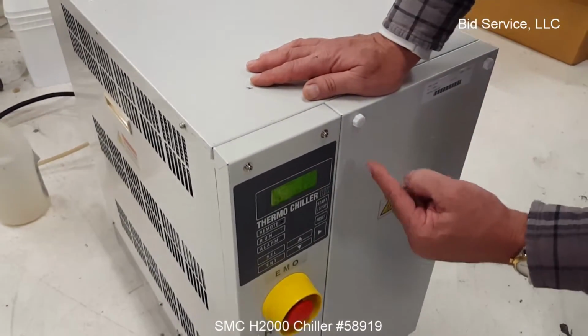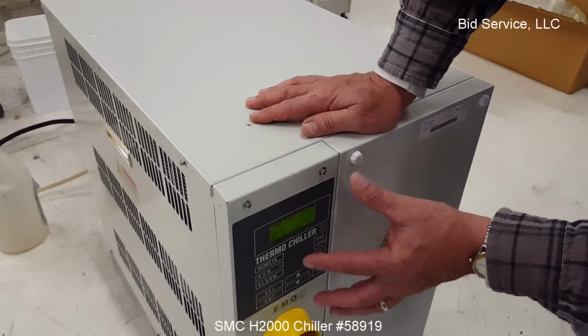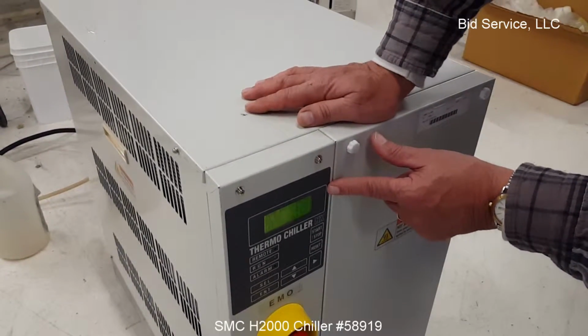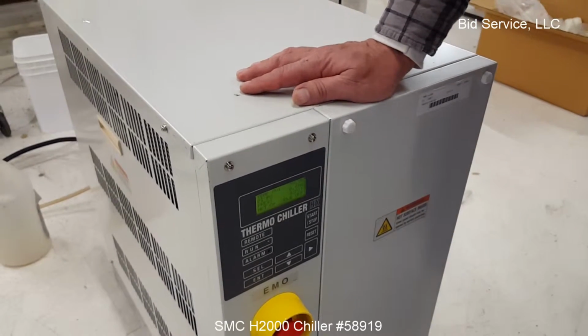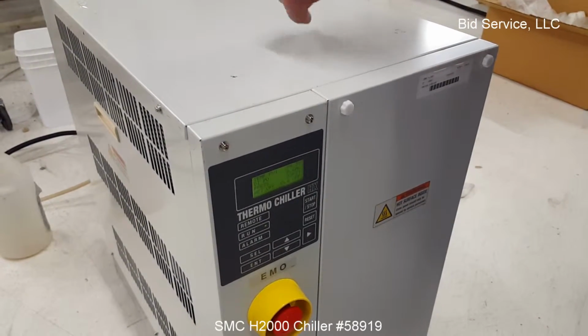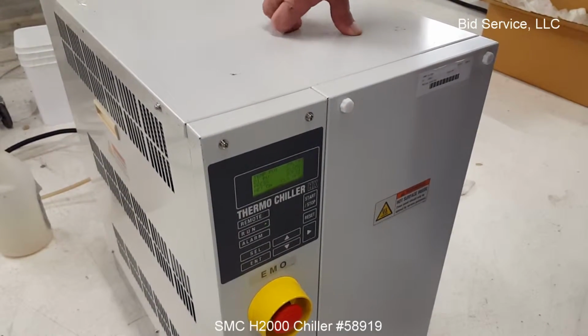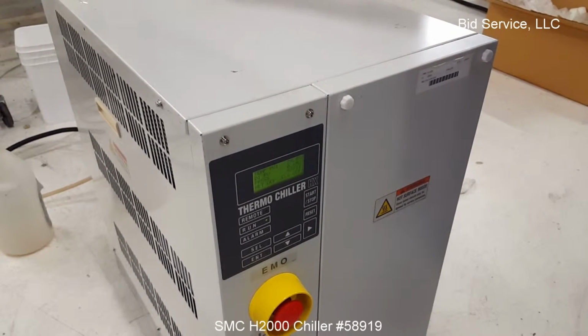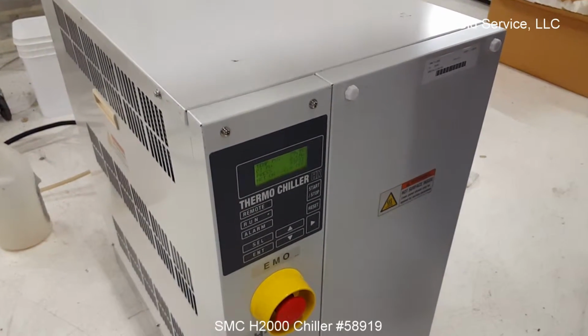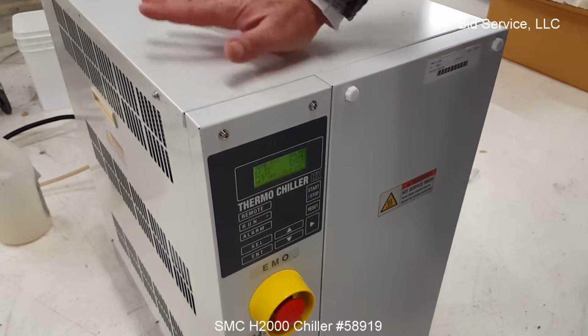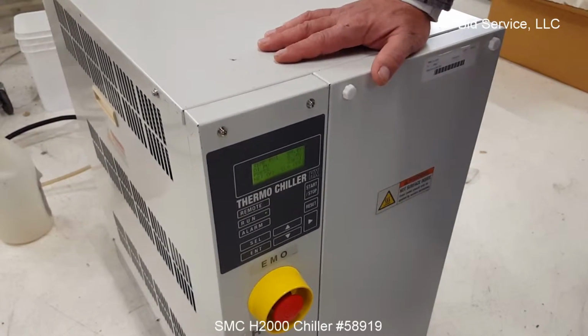And I have it up at the high end so you can see that it can go up there and control, which it is, which means that you have the reprocessed fluid recirculating through the heat exchanger, and you have the chiller from an external chiller that I have hooked up, which is not included with this unit.